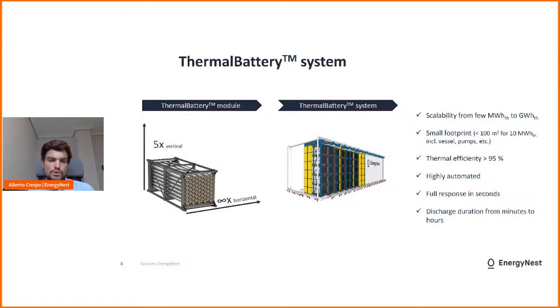Now, based on these modules, depending on the specifics of the project, we can arrive at the desired energy capacity by simply stacking these modules up to a height of 5, and in principle, as many as you want in parallel. So we can go in scalability from a few megawatt hour to the gigawatt hour scale, for example, in utility scale applications. In terms of a small footprint, due to this stacking, we are pretty good, I would say, with a 10 megawatt hour storage system being below 100 square meters of footprint, including all the ancillary equipment, such as valves, the pumps, etc.